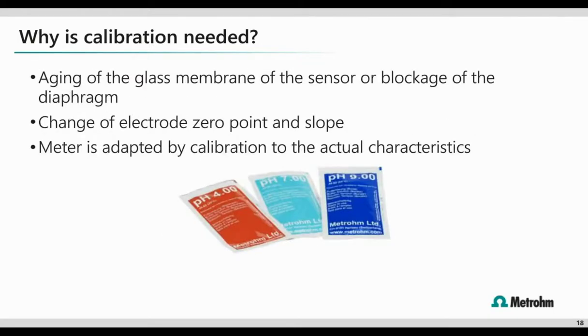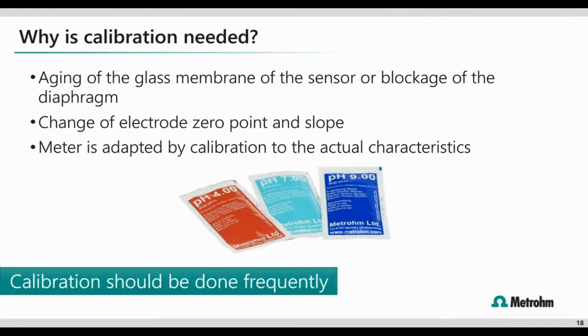Now, remember those are ideal values and they'll change as a result of the aging glass membrane or a change in the diaphragm system. So for this reason, a pH meter or device, whatever you're making the calibration or pH measurements with, must be adapted to the characteristics of the electrode. When we calibrate, we're not actually making any changes to the electrode per se. We're adapting the system to the electrode conditions. So all of this is to say, make sure we're calibrating at regular intervals and using fresh buffer solutions.